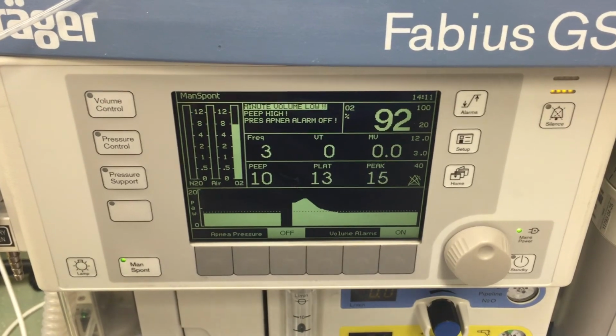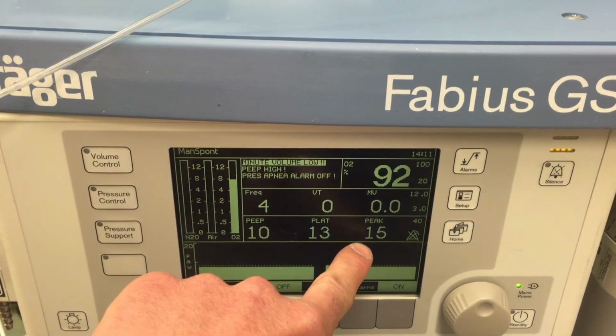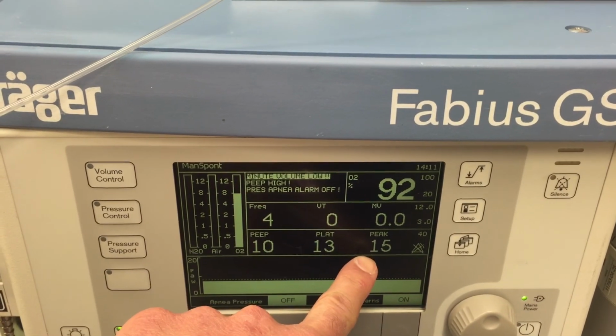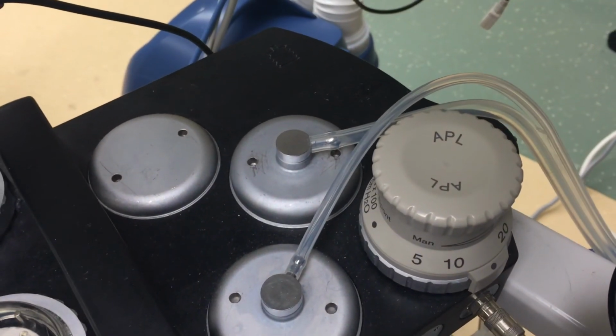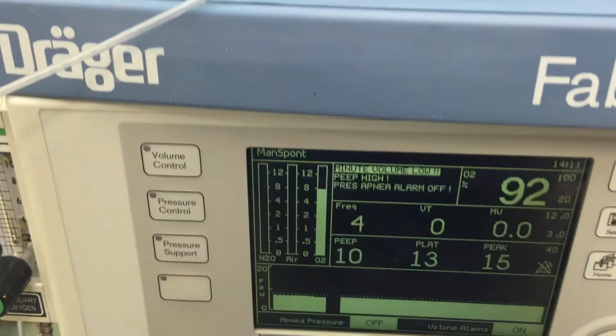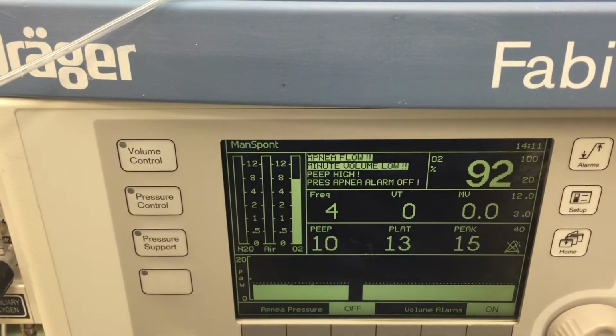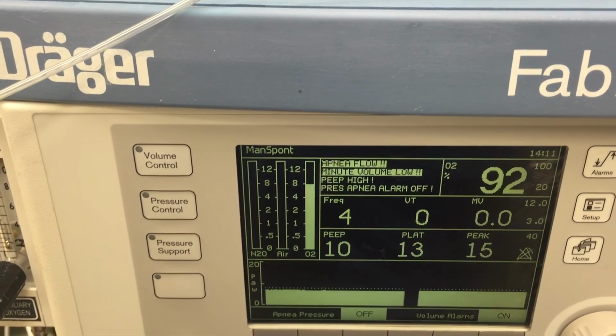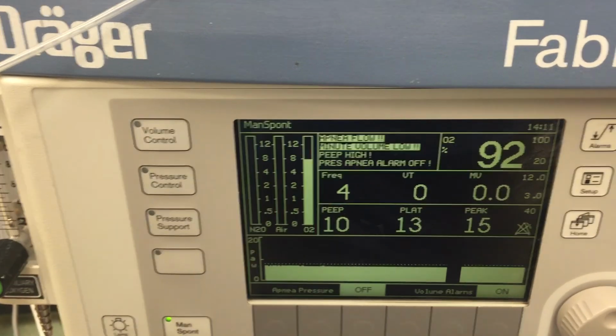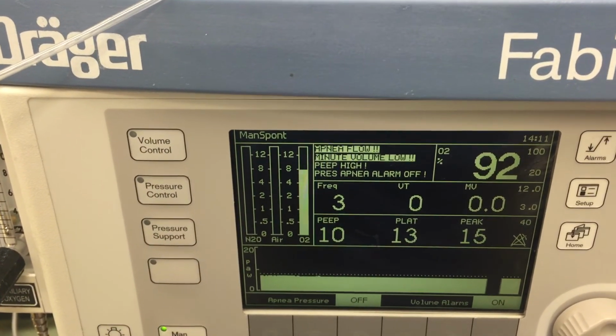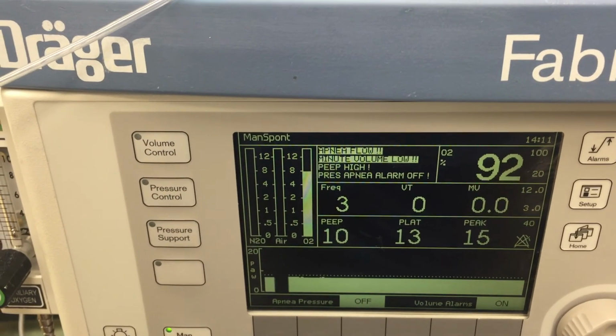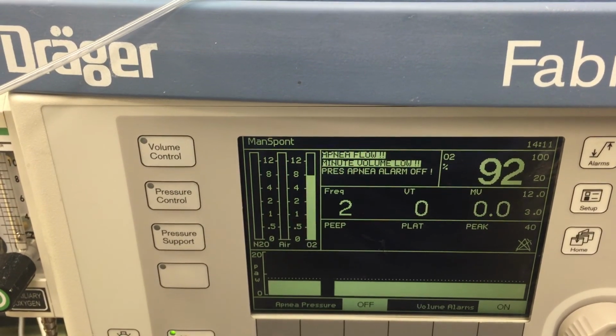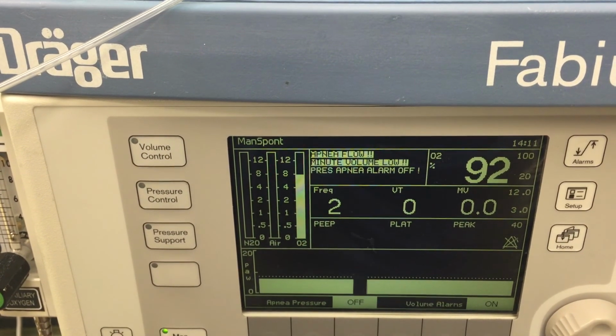The next parameter you want to look for is peak airway pressure, shown here 15. This should correlate with the pop-off valve, which shows 15 as well. If the two correlate, that means there are no leaks in the system and a continuous pressure is being built up. If this was less than 15, that would mean that not all the pressure is being generated to the anesthesia machine and that there is a leak in the system.